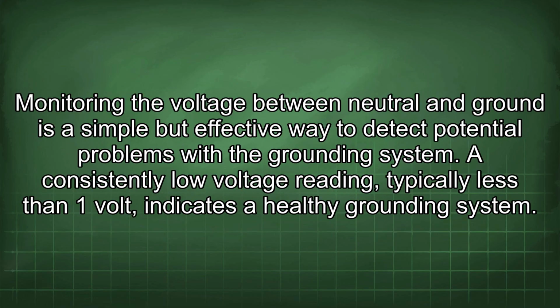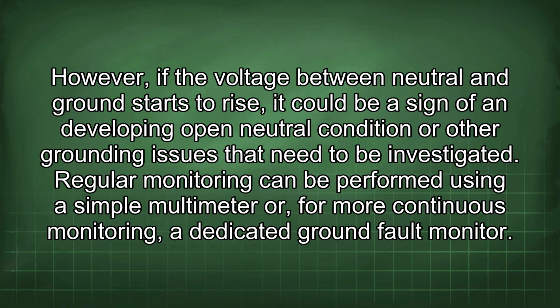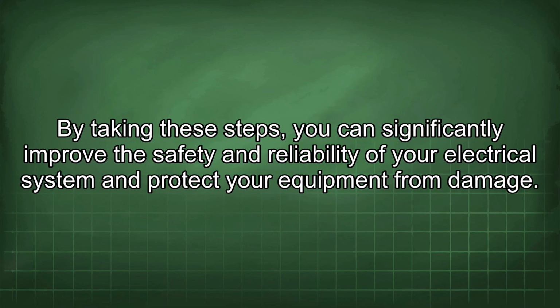Monitoring the voltage between neutral and ground is a simple but effective way to detect potential problems with the grounding system. A consistently low voltage reading, typically less than 1 volt, indicates a healthy grounding system. However, if the voltage between neutral and ground starts to rise, it could be a sign of a developing open neutral condition or other grounding issues that need to be investigated. Regular monitoring can be performed using a simple multimeter or, for more continuous monitoring, a dedicated ground fault monitor. By taking these steps, you can significantly improve the safety and reliability of your electrical system and protect your equipment from damage.